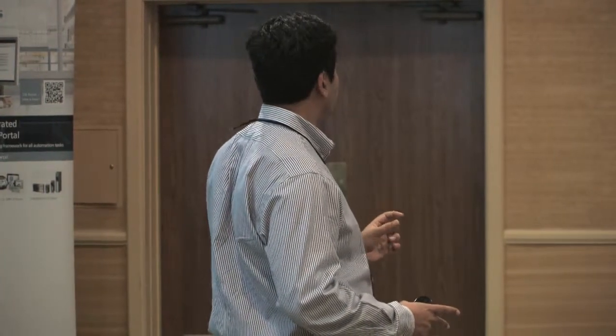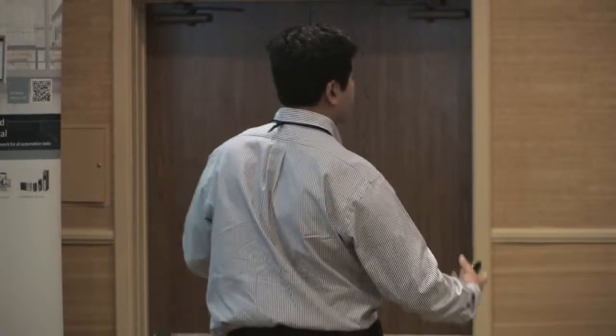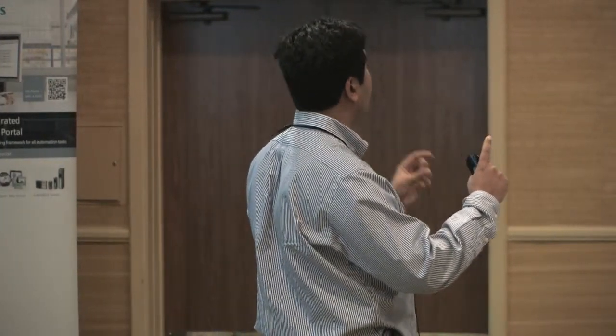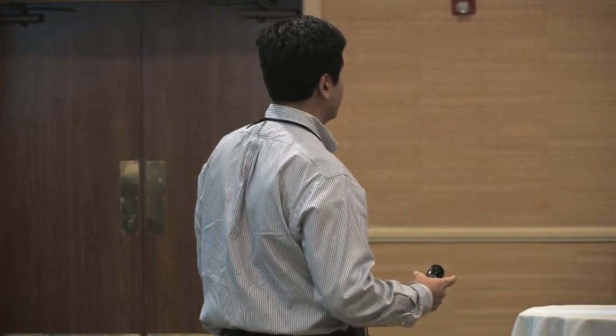All right? What is the advantage to that? It's reducing downtime, making it more efficient, making it more flexible. 3 o'clock in the morning, stuff happens. And I have the local maintenance guys walking around, and production is down. Do I really want to get out of bed and go to the office and troubleshoot a network? Not necessarily. So I would rather have that guy pull out the C plug, which stores the local config of the device that was working fine before, replace that device with an entirely new similar switch, plug in the C plug, and I'm up and running in no time. Those are the advantages when we talk about industrial communications.